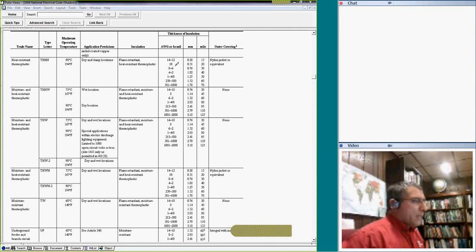Let's look at this one, guys. THHN, you guys remember THHN? THHN is for a dry or damp location, rated 90 degrees. Why is it 90 degrees? Because this table says so. Look at this, guys. It's THWN. If you use it in a wet location, it's 75. That's how they catch you on the test. If you use it in a dry location, it's actually rated for 90 degrees. In a wet location, 75; in a dry location, 90 degrees.